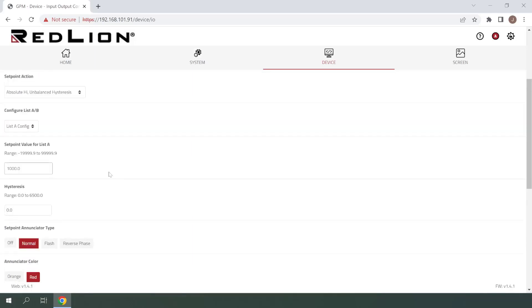The next setting is Setpoint value for List A. This is the value that will be compared to the measured value in order to trigger the setpoint alarm. I'll enter a value of 300 here, which will trigger our setpoint alarm when the PM50 measures 300 GPM or greater.